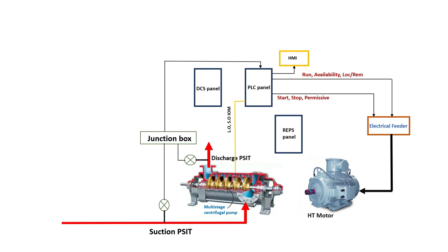We also have rotary equipment protection systems. The basic signals for these systems include vibration parameters, winding temperature, keyphasor, accelerometer, velocimeter, etc. These rotary equipment protection system instruments protect both the motor and the pump during any abnormalities. They generate an ESD trip signal that goes into the PLC panel, and the PLC panel in turn trips the electrical feeder systems.